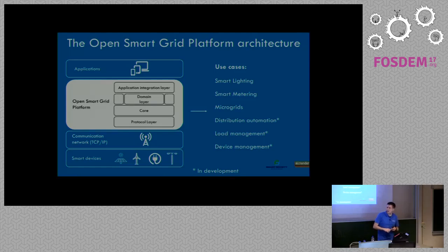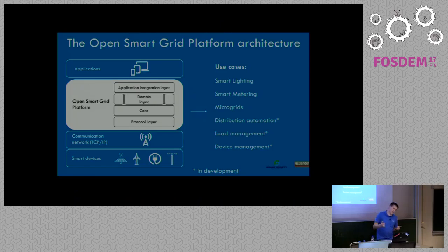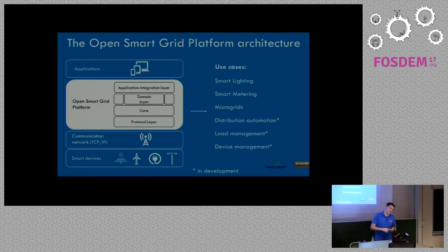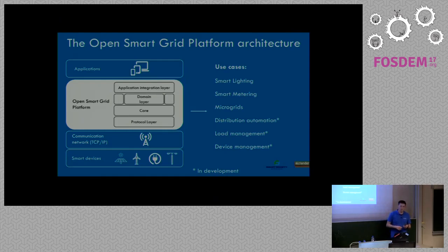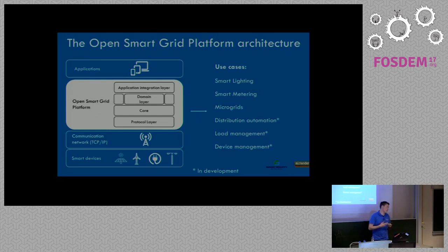Load management is something we're working on — especially relevant in Germany where sometimes there's too much solar power and the utility wants to switch off certain solar panels. That could be done with the OpenSmartGrid platform as well. The platform also contains device management so you can see which devices are connected. Right now there are multiple protocols connected: DLMS COSEM for smart metering, IEC 61850, and the Open Streetlight Protocol for smart lighting.